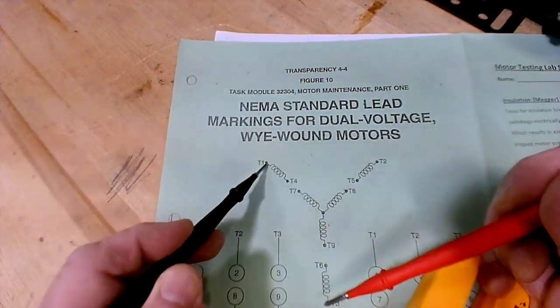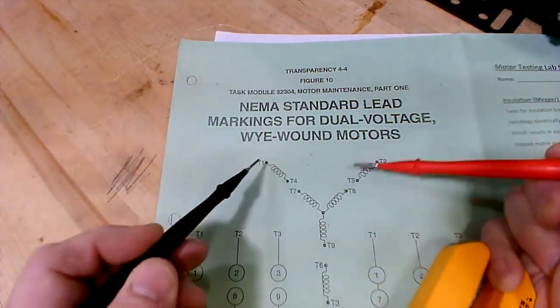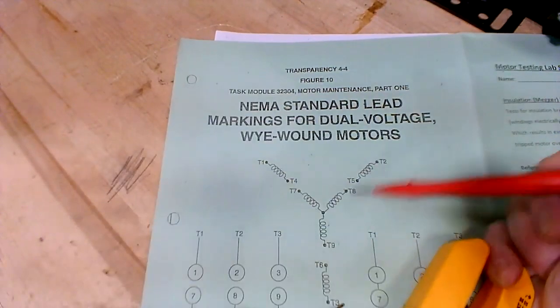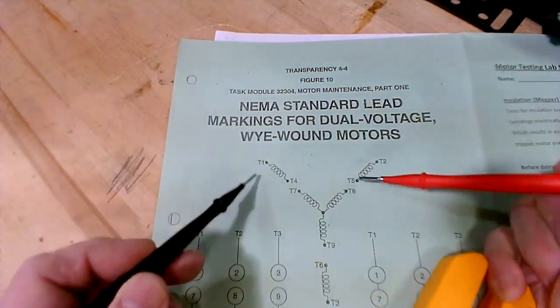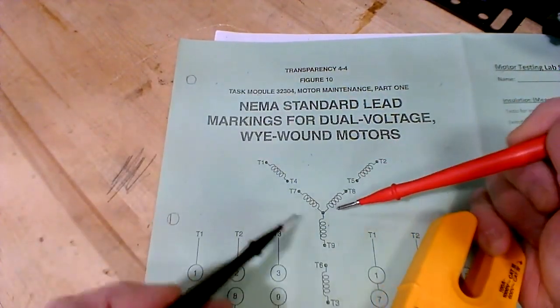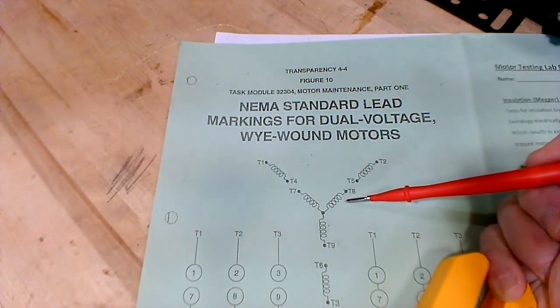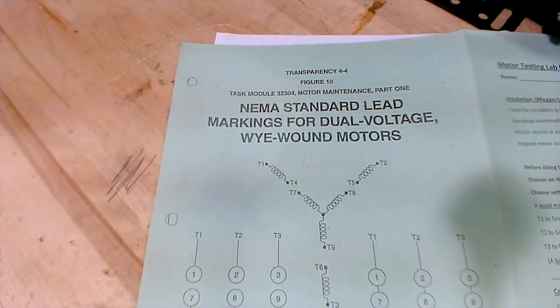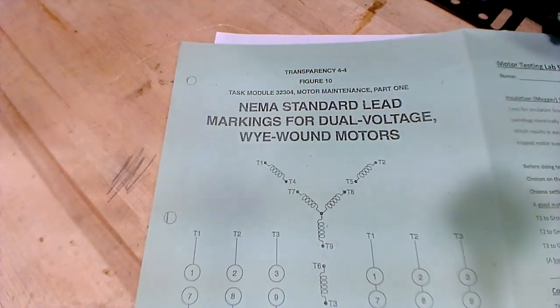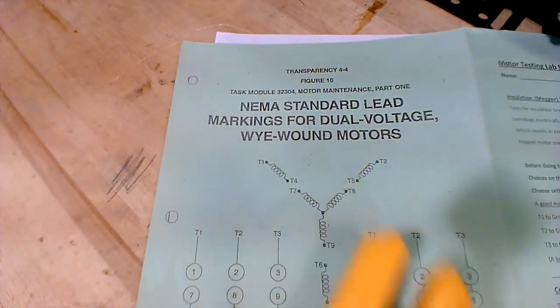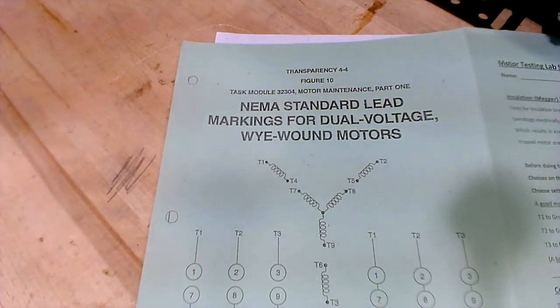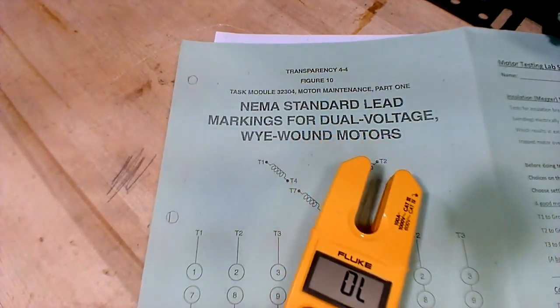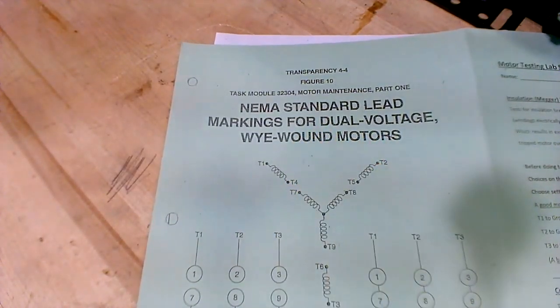And then you can check from 1 to 3. You check the three directions here, here, and then here. And if you get OL on any of them, you've got a burned up winding in that motor. So that's your second test there, checking leg to leg through it with no power on it. Okay, so let's check a good one, then we're going to check a bad one.